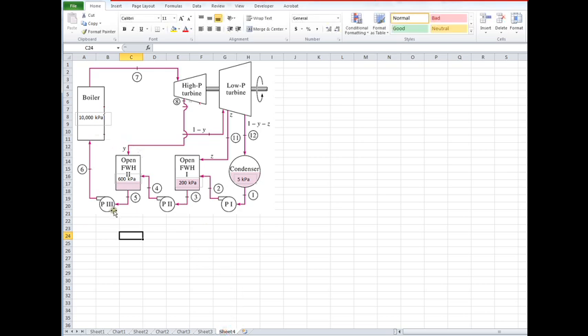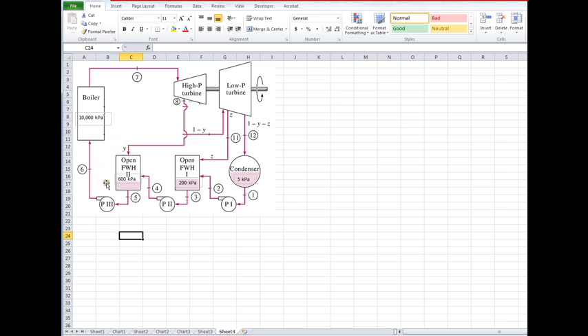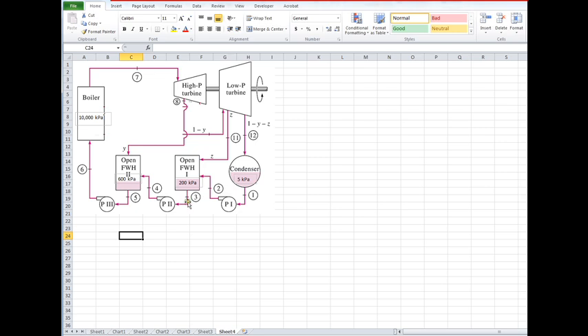And think about putting a control volume on this first feedwater heater. Now remember what I said: if we have multiple feedwater heaters, we want to always start with the one that's closest to the boiler. That's going to isolate this first unknown fraction and will allow us to calculate it separately.